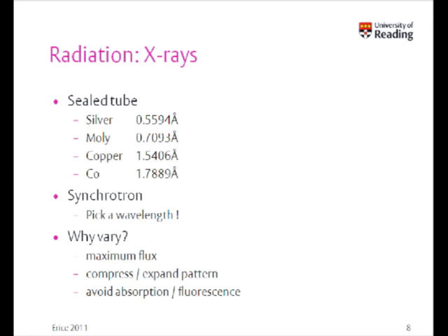So in terms of the choice of radiation, I think most of us will be familiar with copper, either in its unmonochromated or its monochromated form here, in sealed tube form. But we're certainly not limited to that. There are a number of commercially available solutions, from the longer, softer wavelength of cobalt at 1.8 through to the more common and starting to be seen more on powder diffractometers, molybdenum radiation, on the same footing as single crystal, and for even harder radiation and possible PDF work to get you out to very high spatial resolution, 0.56 angstrom silver radiation.